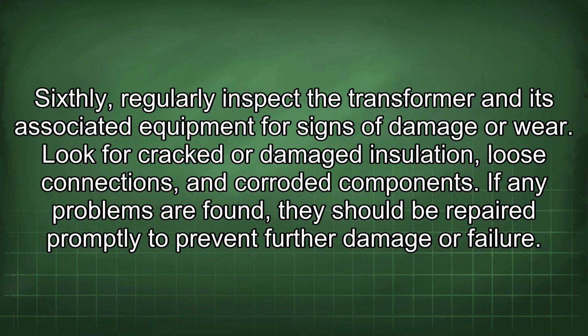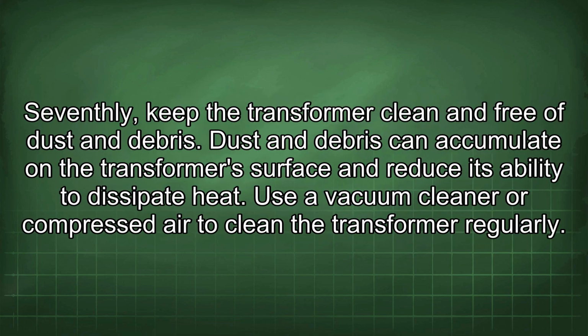Sixthly, regularly inspect the transformer and its associated equipment for signs of damage or wear. Look for cracked or damaged insulation, loose connections, and corroded components. If any problems are found, they should be repaired promptly to prevent further damage or failure. Seventhly, keep the transformer clean and free of dust and debris. Dust and debris can accumulate on the transformer surface and reduce its ability to dissipate heat. Use a vacuum cleaner or compressed air to clean the transformer regularly.